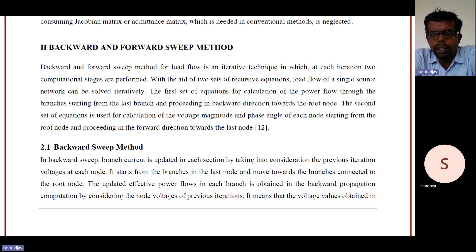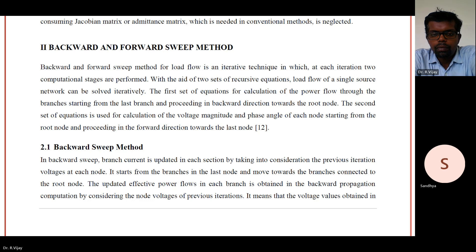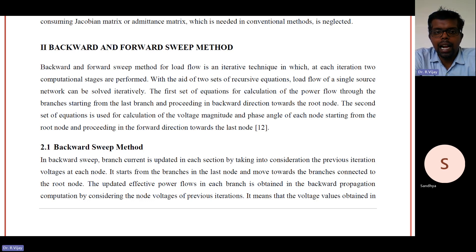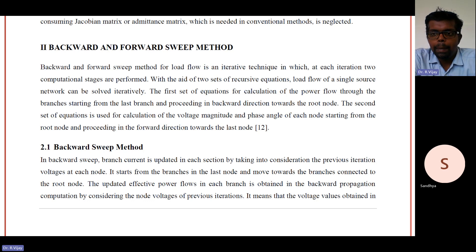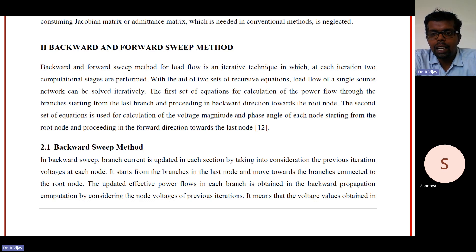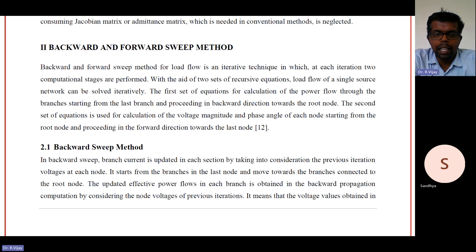With two sets of equations, we are going to solve this problem. The first set of calculations covers the power flow through the branches, starting from the last branch and proceeding in the backward direction towards the root. That is why this algorithm is called the backward sweep method. The second set of equations is used for the calculation of voltage magnitude and phase angle of each node, starting from the root node and proceeding in the forward direction.